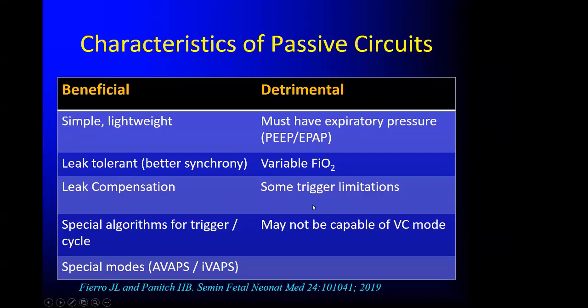Depending on your machine, you might have some limitations with how you trigger the passive circuit. I mentioned those algorithms, but depending on the machine, you may not be able to deliver a volume-controlled breath. So the Trilogy will allow you to use a passive circuit in volume control. The Astral will not. If you wanted to use a special mode, like average volume assured pressure support or intelligent volume assured pressure support, you have to use a passive circuit.